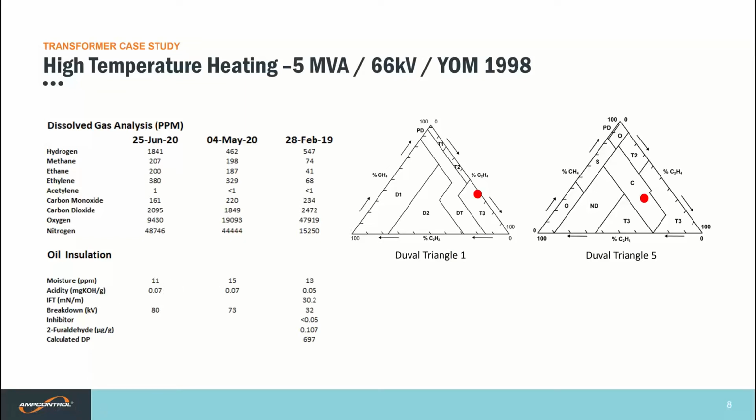The acid levels are not low, and levels are questionable according to guidance from Myers. And their classification system is more stringent than, for instance, IEC 60422. So this prompted me to recommend closer monitoring of furan test data to evaluate the effects of the acid levels upon the condition of the paper insulation. Decreases in DP would be an additional prompt for us to recommend Fuller's Earth filtration to clear the oil of the acid.